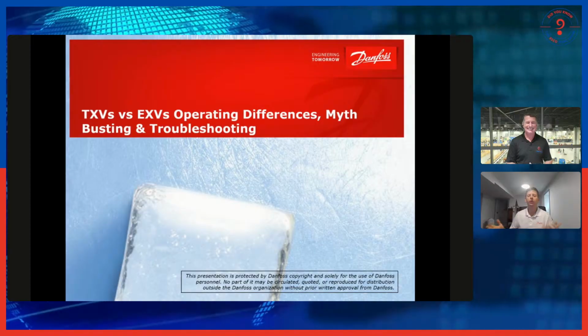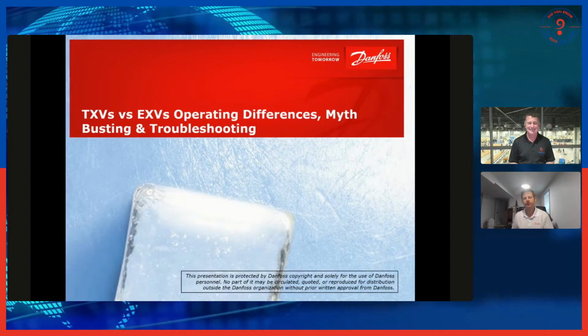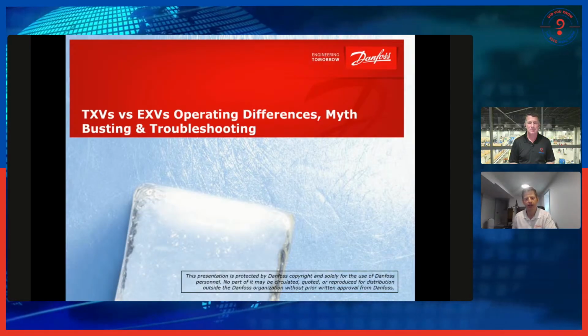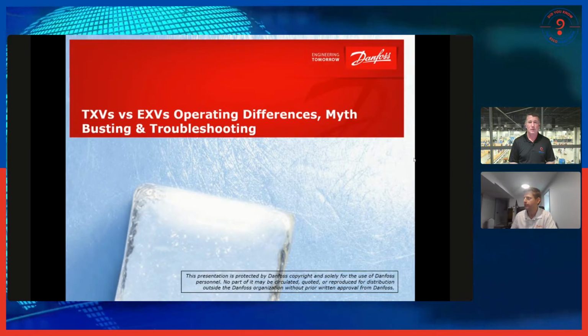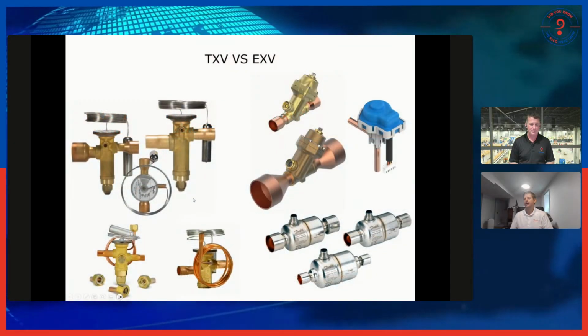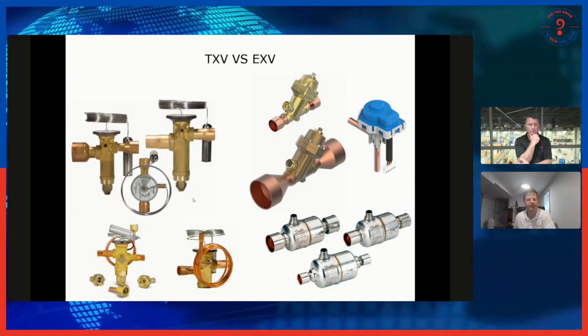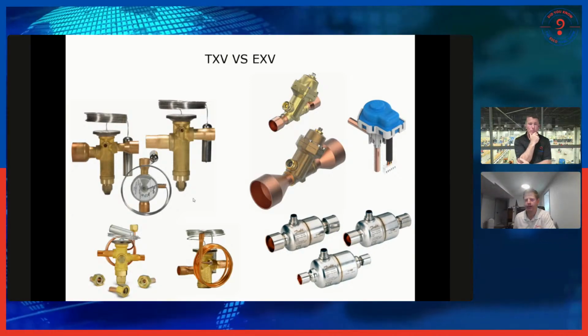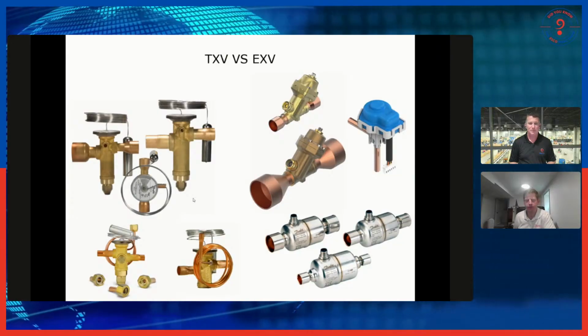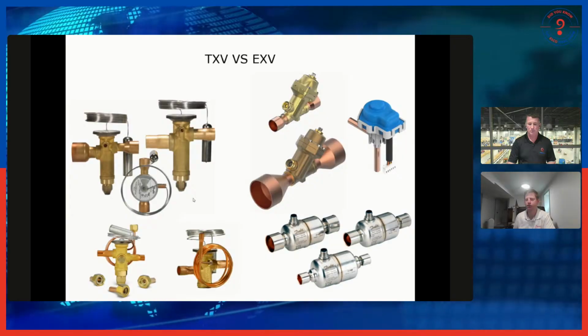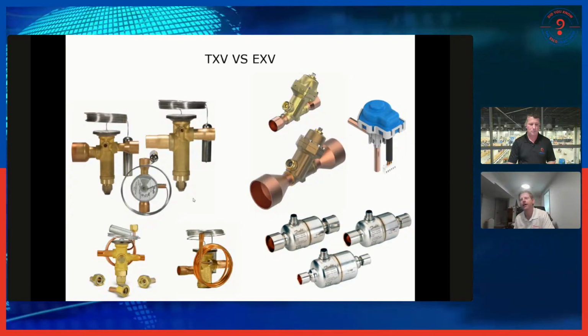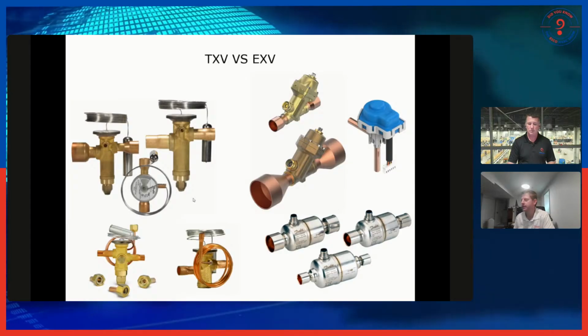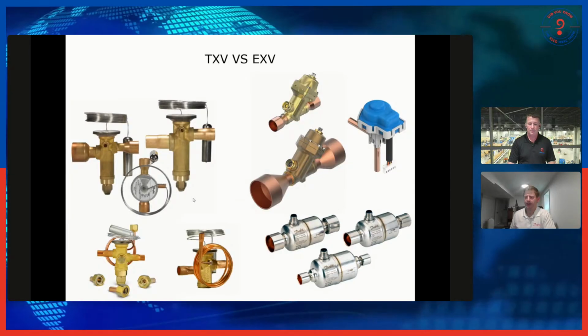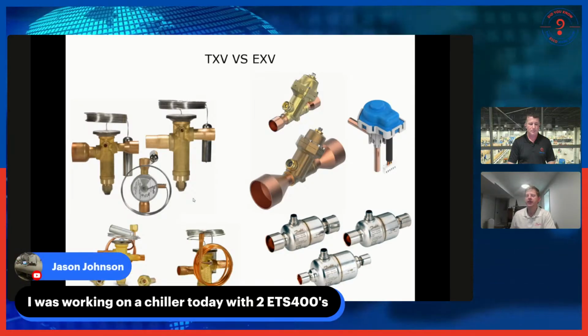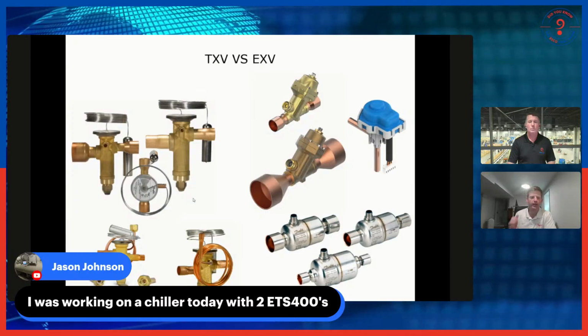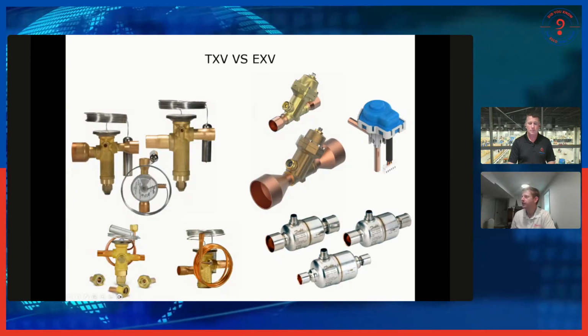Absolutely. So, the goal today is to talk about TXVs versus EXVs, get a little bit into the operating differences, myth busting, and close out with some troubleshooting. I've got up here some pictures of different TXVs and EXVs made by Danfoss, but TXVs and EXVs work in pretty similar ways between different manufacturers. So everything I say here should be, for the most part, pretty interchangeable with different manufacturers of TXVs and EXVs. The main thing I want to start off with is, why do manufacturers choose a TXV versus an EXV, and when are there advantages versus disadvantages of either product?